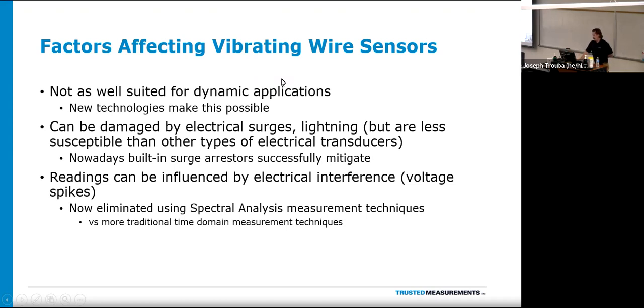And then readings can be influenced by electrical interference, such as pump motors, power lines, things like that. So we can do things like shield the instrument. You can shield magnetically in a metal pipe and things. You can shield the cable itself. There's ways to get around this issue. And now we have new technology called spectral analysis, which can actually take the noise out of the vibrating wire signal. And you can really dial into what it's actually measuring and filter out that noise from electrical interference or a variety of other interferences that sometimes occur.